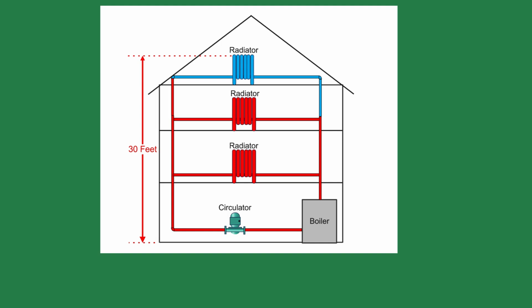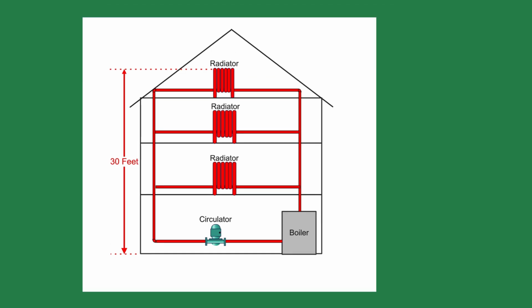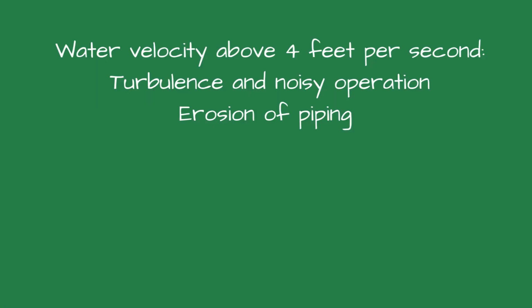The speed of water affects how efficiently heat is transferred from the boiler to the terminal units. If the water moves too slowly, it loses heat too quickly, especially in the long runs, and may not deliver enough warmth to the far zones. On the other hand, high velocity may not allow enough time for heat transfer in the radiators or heat exchangers, reducing comfort. Water moving too fast, typically above 4 feet per second in copper tubing, can cause turbulence and velocity noise, the rushing or whooshing sound you hear in piping.